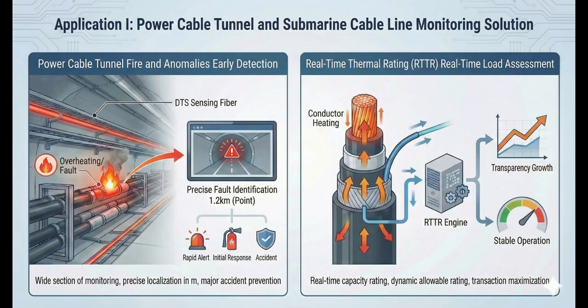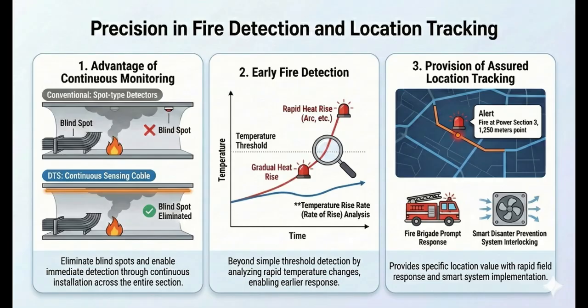One is early detection of fire and abnormal overheating. It continuously monitors along cable trays and immediately reports abnormal temperature and location. The other is load optimization based on RTTR. By reflecting the actual thermal condition of the cable, RTTR calculates the safe operating capacity, improving asset utilization and enabling more precise operational decision-making. The advantages of DTS in utility tunnel monitoring can be summarized in 3 points.